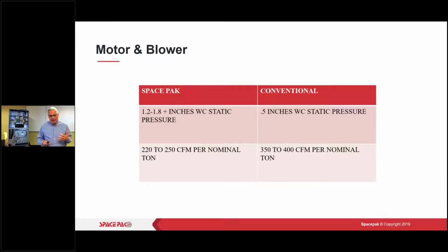I want you to think of SpacePak as a big balloon, and this balloon is under pressure, but it's a special balloon. And if I poke holes in the balloon, it doesn't pop, but I would have equal air pressure coming out of my balloon. And that's called static regain, and we're pressurizing our plenum, and that's what we're doing. So I should get the same airflow out of all of my drops. So you can see on 1.2 to 1.8 static versus half on conventional, and on 220 to 250 CFM versus 350 to 400 on conventional.